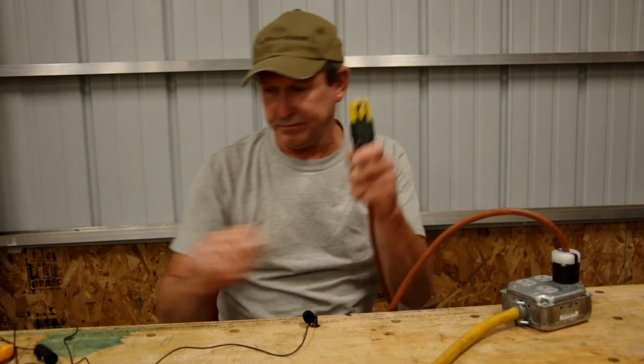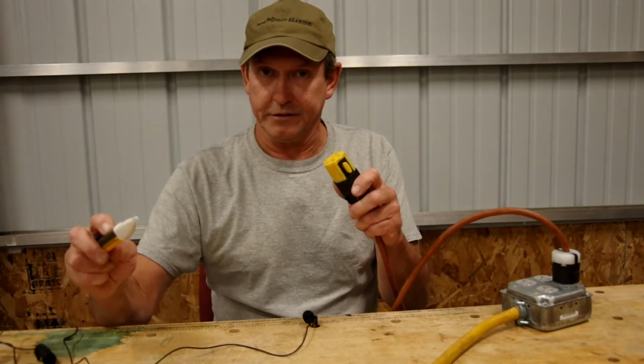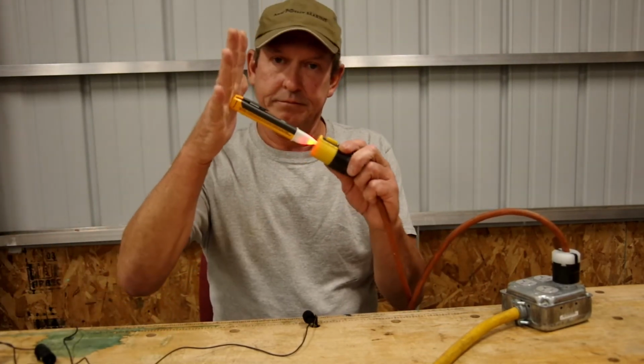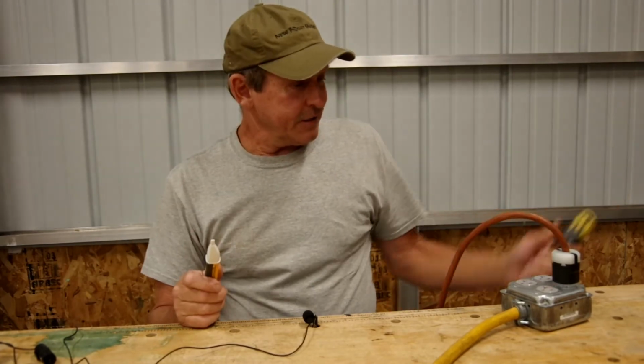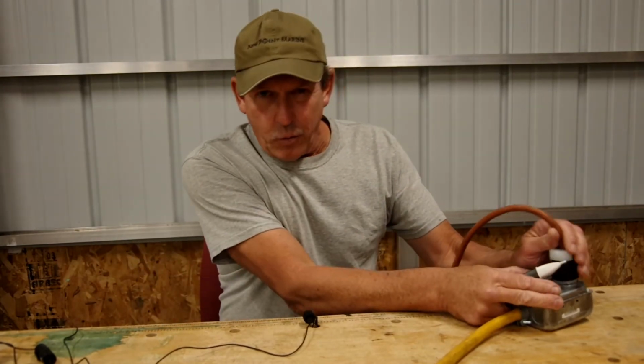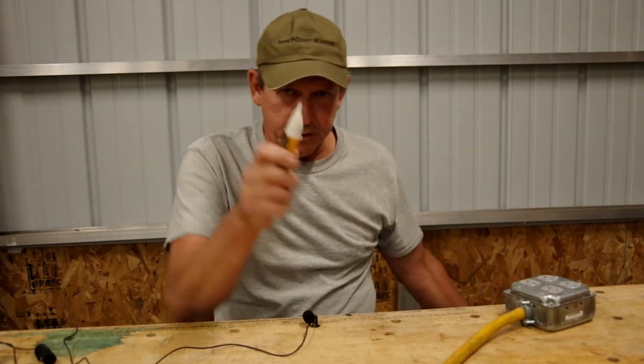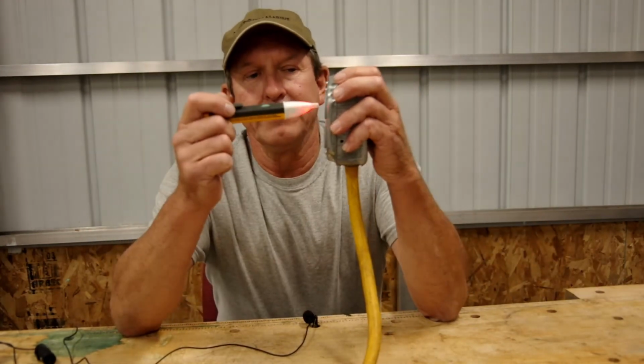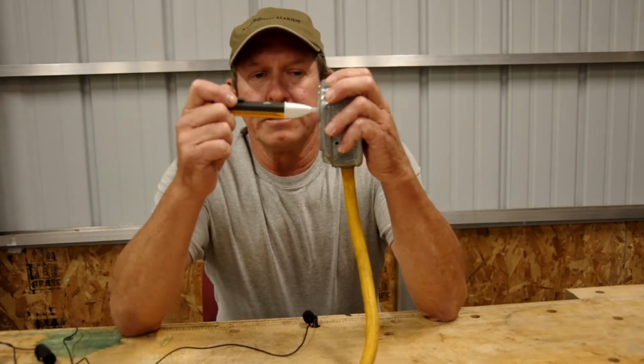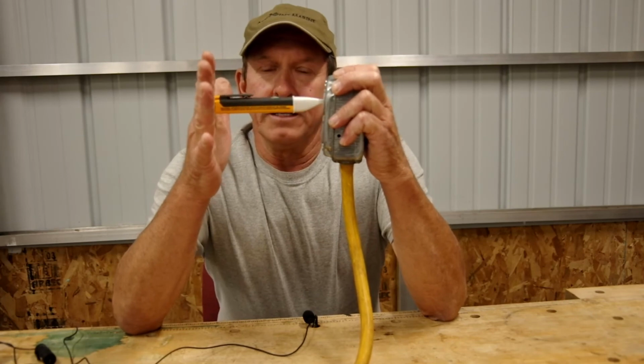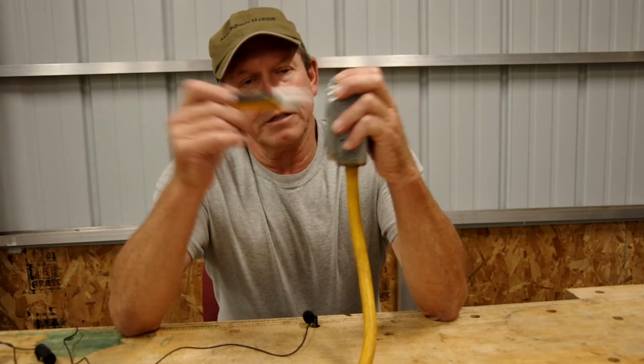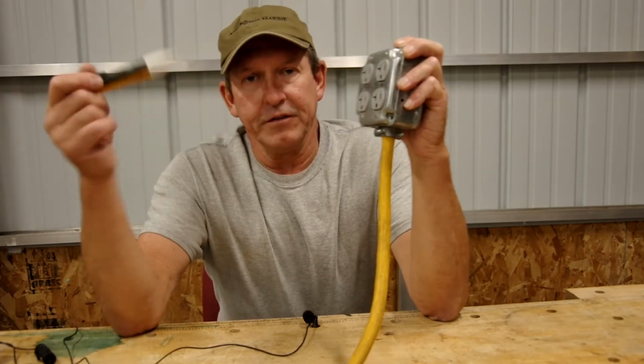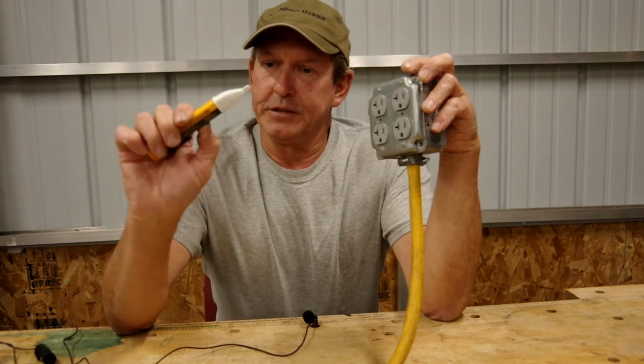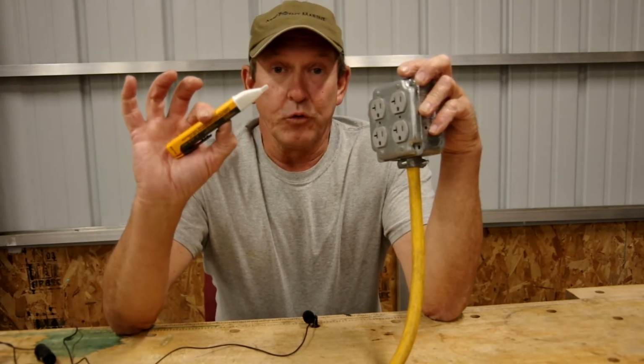Now, check this out. So just something to be aware of, because if you're using one of these and ask, is this outlet de-energized, you might think yes it is. But this tamper-resistant safety feature can give you a bit of a false reading.